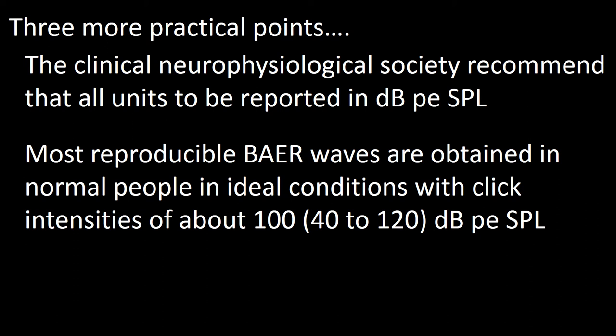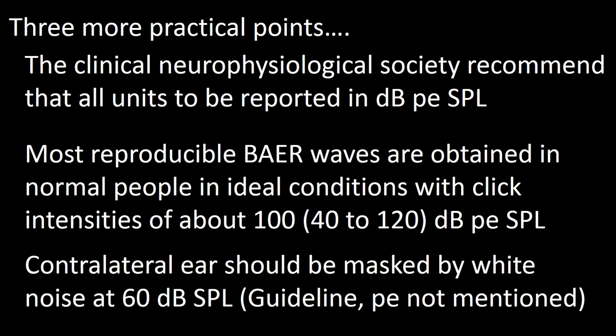Three more practical points before leaving this conversational section. One: the Clinical Neurophysiology Society recommends that all units be reported in dB PE SPL. Two: the most reproducible brainstem auditory evoked response waves are obtained in normal people under ideal conditions with a click intensity of about 100 dB PE SPL. Three: the contralateral ear should be masked by white noise, and the Academy recommends 60 dB SPL as the intensity of the noise. In the guidelines, there is no mention of PE before the SPL for this parameter.